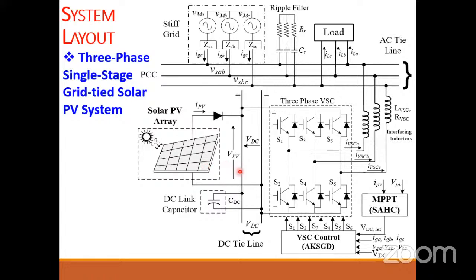On the merit side, here you can say a smaller number of switches is required, right? So you can say the loss is a little bit lower with respect to the two stages, but yes, here the panel requirement is higher with respect to two stages, right? So this is the merit and demerit. And there is another demerit here with respect to two stages. Here, suppose the 700 volts on the DC link is the operating voltage. This voltage is the PV MPP voltage.